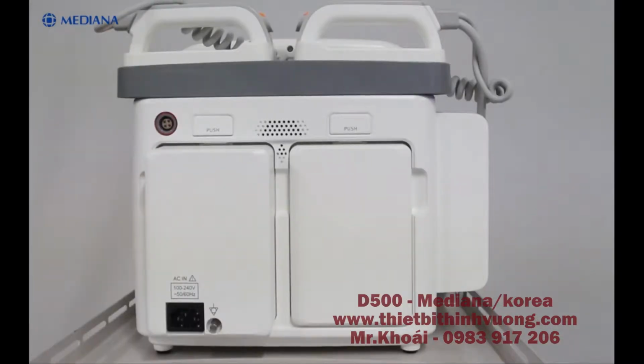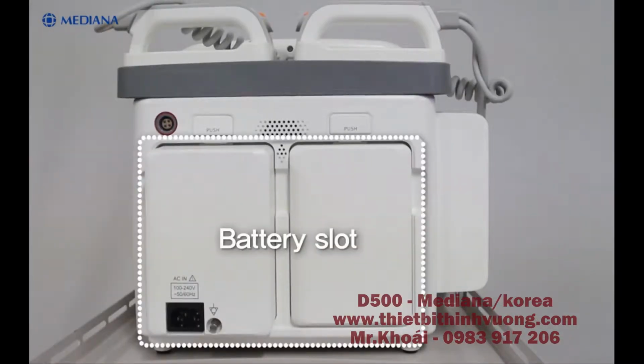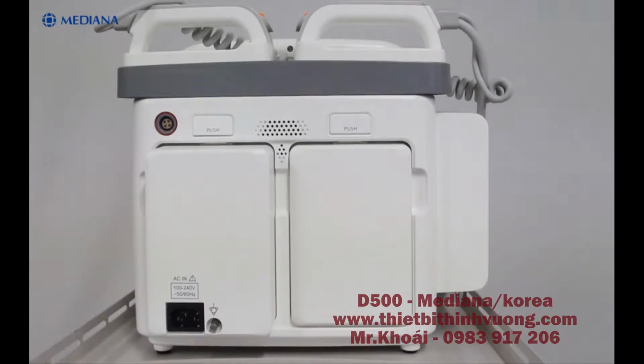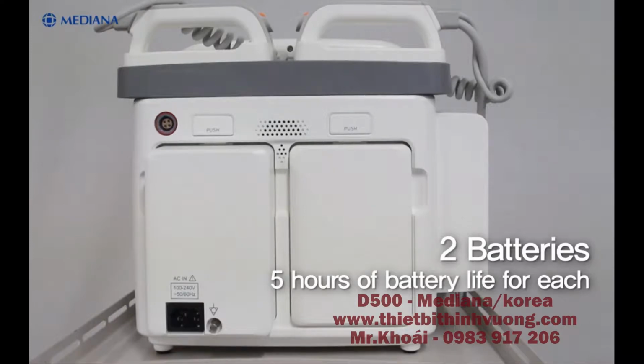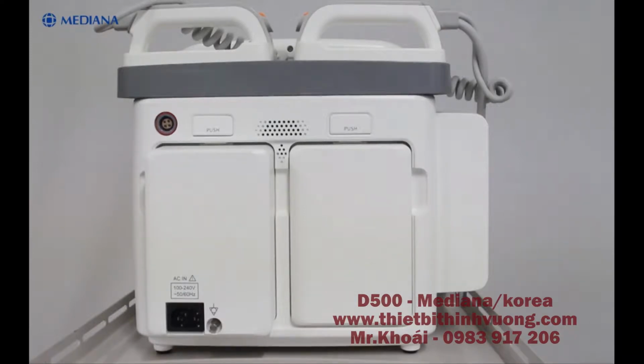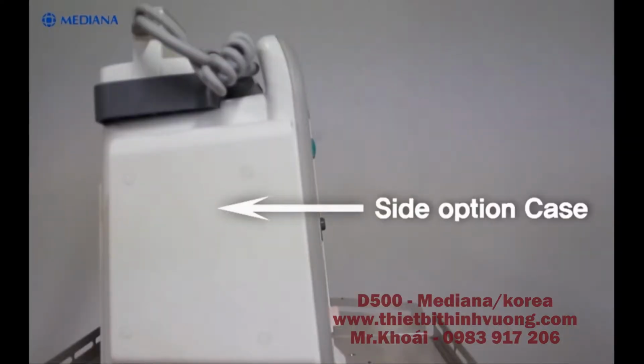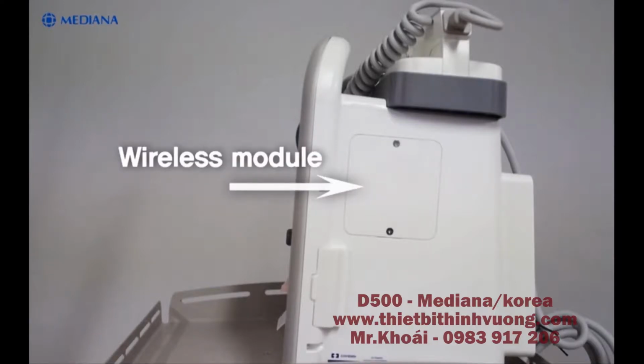Across the rear panel, you can see 2 battery slots and the push buttons. You can operate the D500 with 2 batteries, 5 hours of battery life for each, so you have 10 hours of operating time with 2 batteries. And also, you can use the power supply in the left slot. Between the 2 battery slots, we also have a speaker, so you can hear prompts, a DC input connector, ground terminal, and AC power inlet. For the additional components, you can see the side option case to the right, and to the left, we can integrate a Wi-Fi or 3G module and a USB slot, so we can upgrade the unit, and finally, the SD card slot for data transfer.